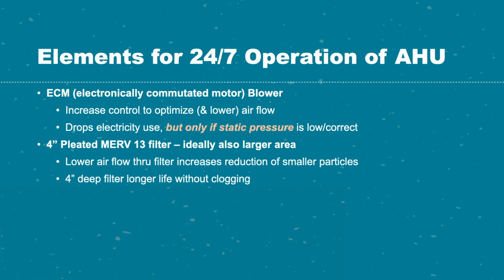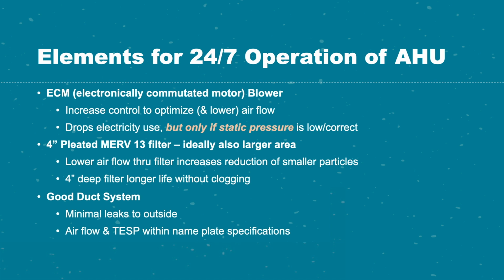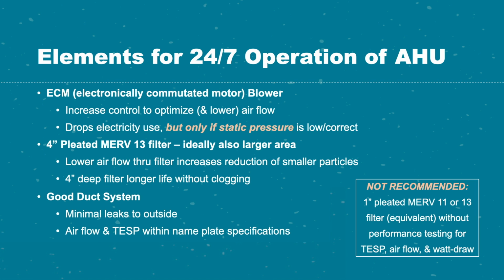So we like the deep filters, 4 or 5-inch pleated MERV 13 filters, but not just the filter in its original size, but also a larger area. And that means that there's less airflow through the filter, and the filter basically performs differently at different airflows. And it's going to reduce more small particles and ultra small particles when it's lower airflow. But you really want a good duct system. You don't want leaks to the outside, and you want the airflow and total external static pressure to be within nameplate specifications. Every HVAC system sold has specs, and systems, when they're installed, they should be checked against those specs.